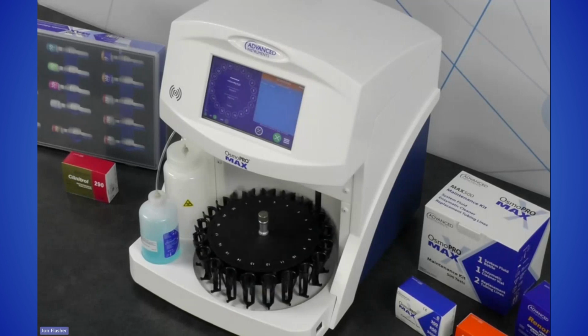There was a question in the chat, is the enzymatic cleaner applied to OsmoPRO? Because the OsmoPRO does not use flow-through technology, because there's no fluidic pathway to accommodate testing on that instrument, it does not. It just requires that the sampler be cleaned regularly. No, the daily QC check is not making adjustments to the calibration.